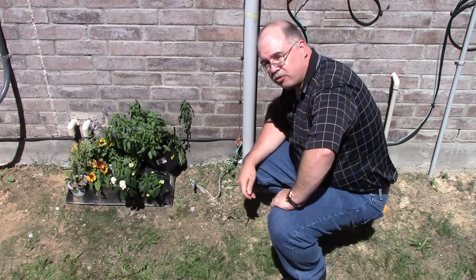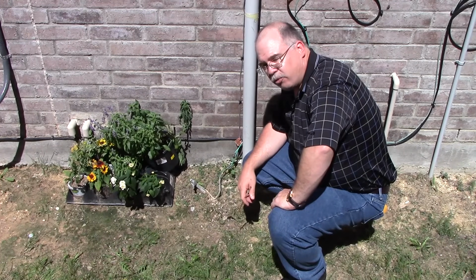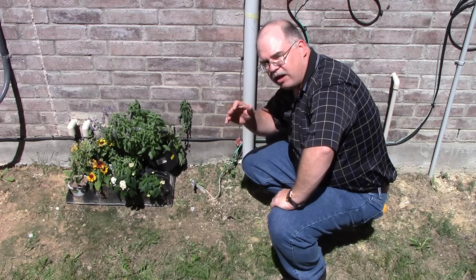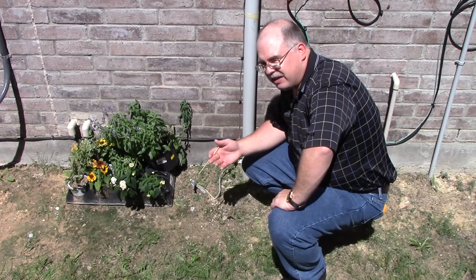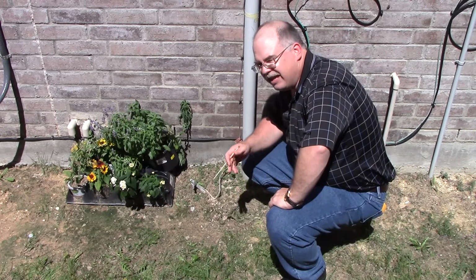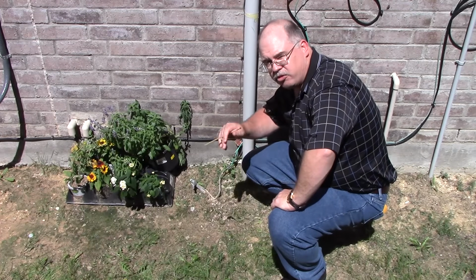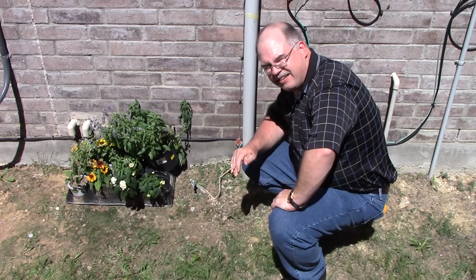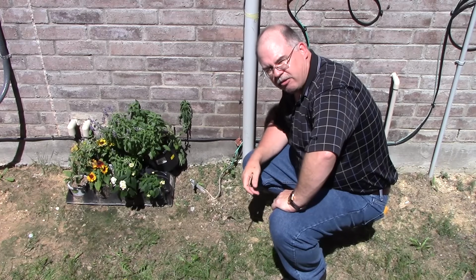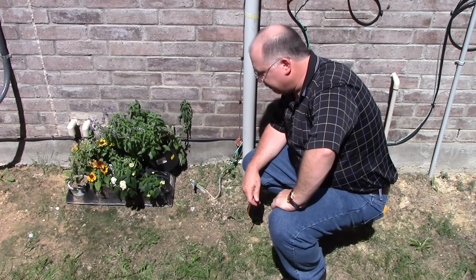Take it away from your electrical system. That's what you have the ground rod for. Don't get confused about driving ground rods at places and thinking that that's going to give you some return path for fault current, because that's not what your grounding electrode system is designed for. Okay, that's what your equipment grounding conductors and bonding jumpers and all that type of thing are designed for.